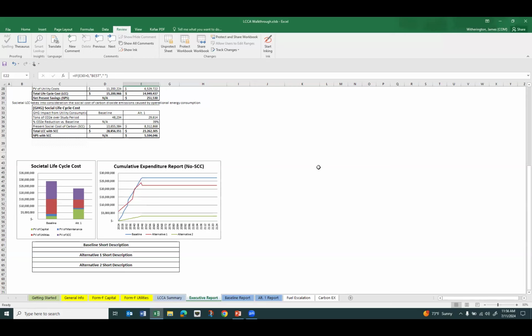Well, and that would be a case where if you're doing the simple payback and using the equation that's provided in the investment criteria presentation, I think someone already posted a link to that, that simple payback calculation includes incremental cost. And for the baseline scenario, if the boiler has 5 years left on it, the baseline scenario should include like for like or code minimum replacement. So that would be calculated in the comparison between the alternative and baseline.